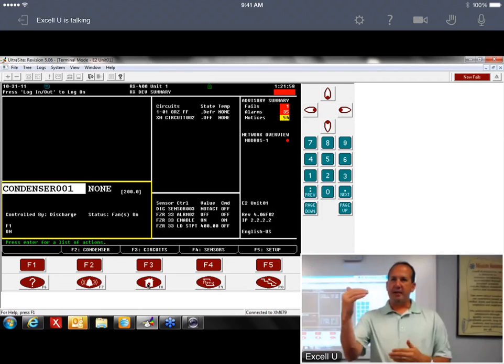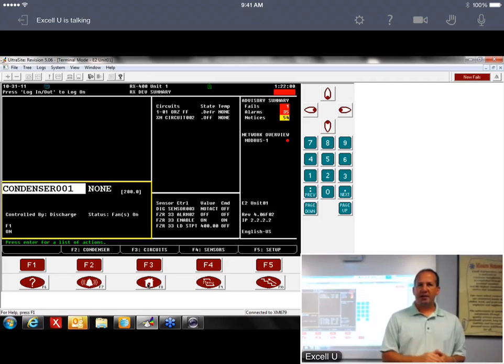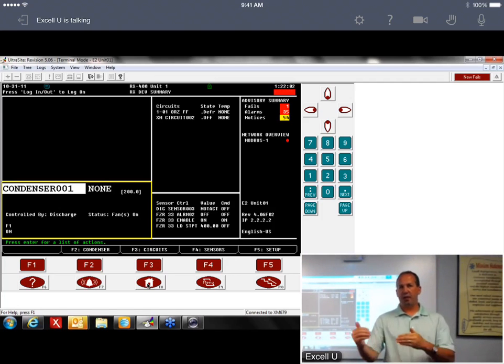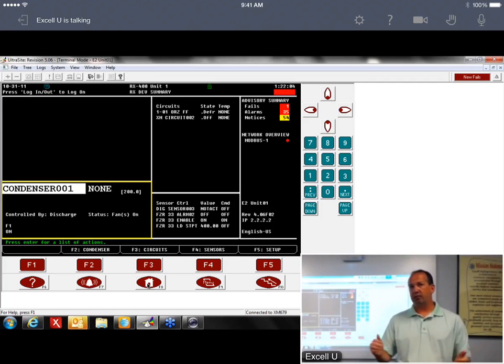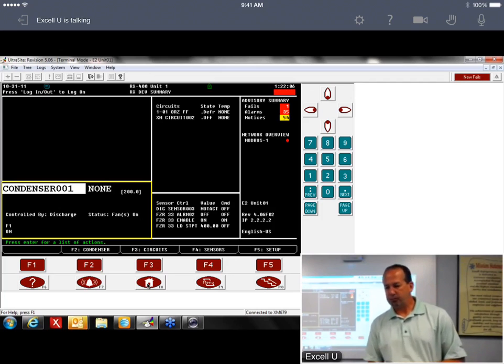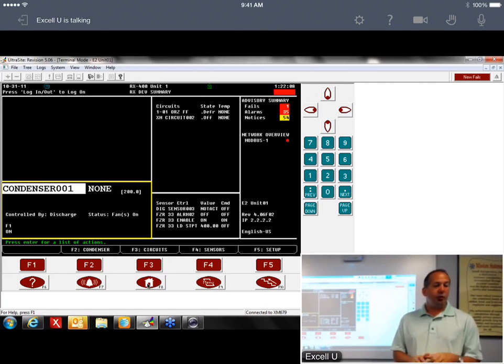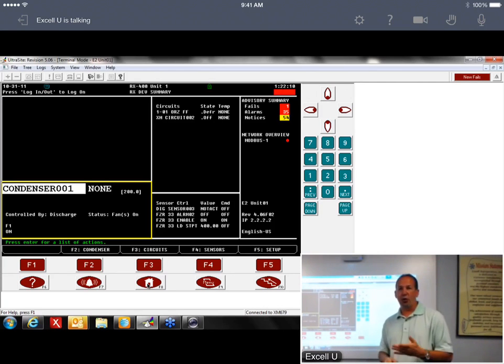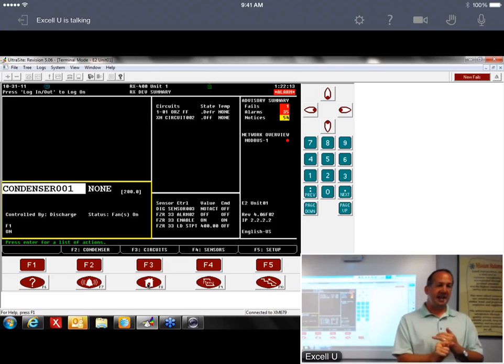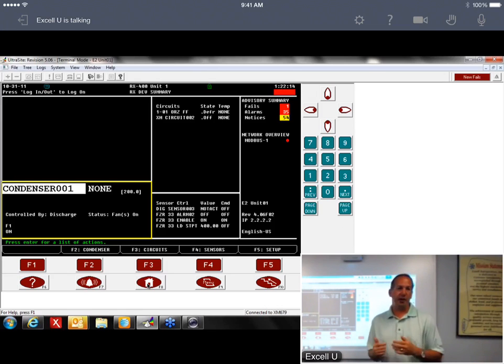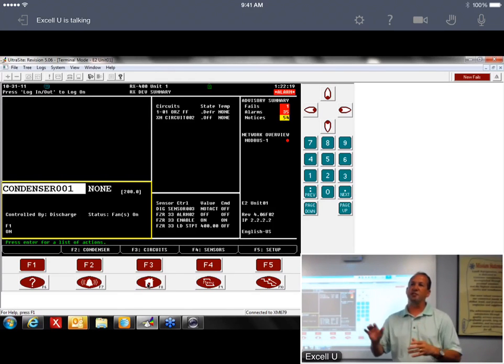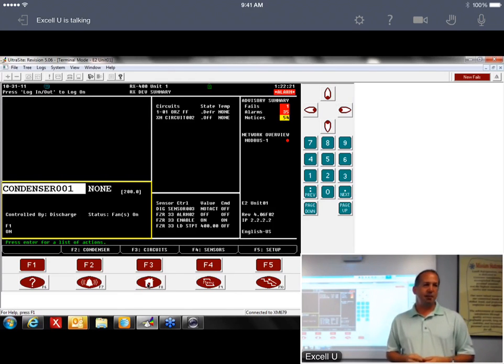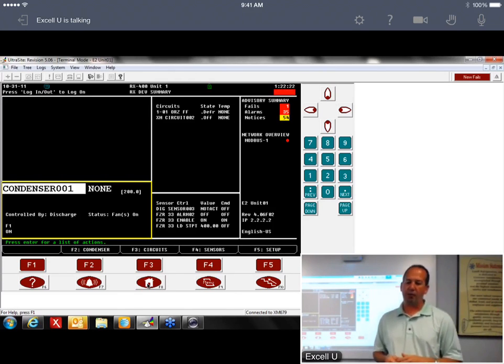Right, yeah, it's basically a top end. So if you say I want to top out at 75%, it'll never be open for the entire time frame. The algorithm that controls the temperature and superheat is an adaptive algorithm. It's kind of a learning algorithm, similar to enhanced suction, where it learns the trends. This does the same thing. It has a learning algorithm.